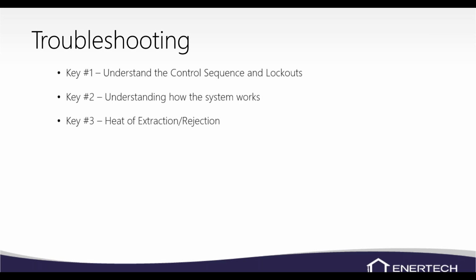Obviously, you need to understand how to calculate heat of extraction and heat of rejection. That's basically our first troubleshooting tool. We can check the heat of extraction or rejection, and that'll tell us the performance compared to what's in the manual. And if it's within specs, then we don't need to throw refrigerant gauges on the system. Throwing refrigerant gauges onto the system when it's in a low pressure lockout, we probably don't want to do that right off the bat. We do have basically a sealed system, kind of like a refrigerator. It's got a certain amount of refrigerant in it. So every time you put your refrigerant gauges on there, you're going to pull some out. So if we don't have to put the gauges on there, we're not going to.